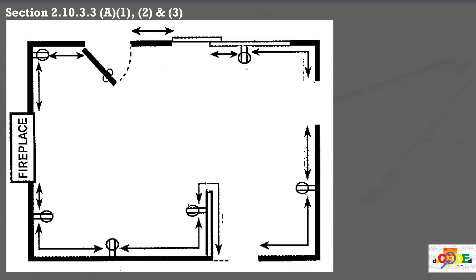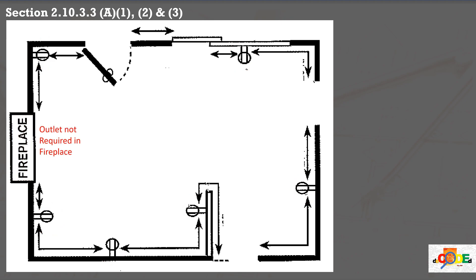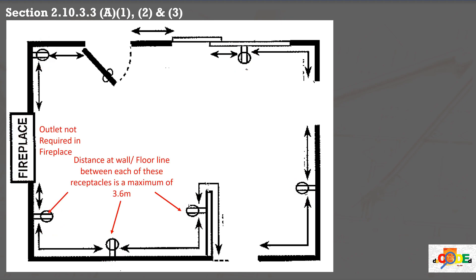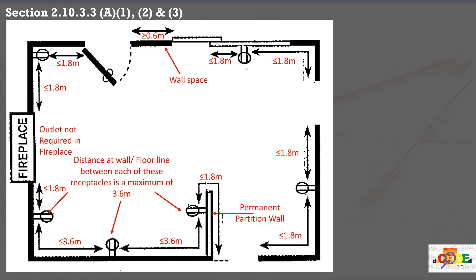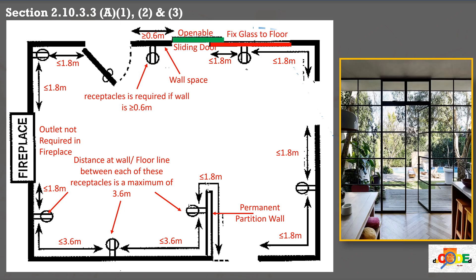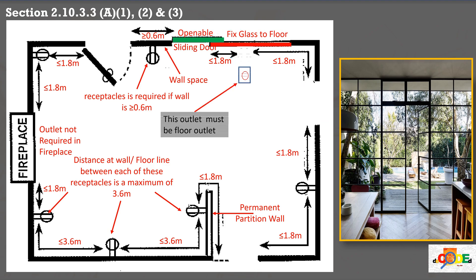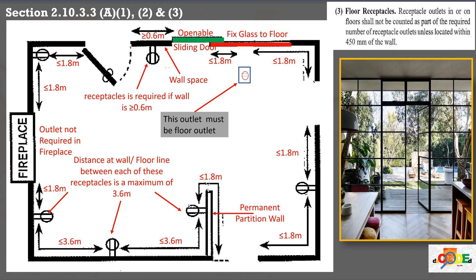Let's look at another floor plan where receptacle outlets are already in place. The fireplace is not considered a wall space. For the long wall, ensure the distance from each outlet is not more than 3,600 mm, then check spacing to see if it complies with paragraph A1. If this wall space is 600 mm or more, an outlet is required. If a fixed panel is full glass and an outlet cannot be installed, use a floor outlet to comply with paragraph A2. In paragraph A3, floor outlets must be within 450 mm from the wall.